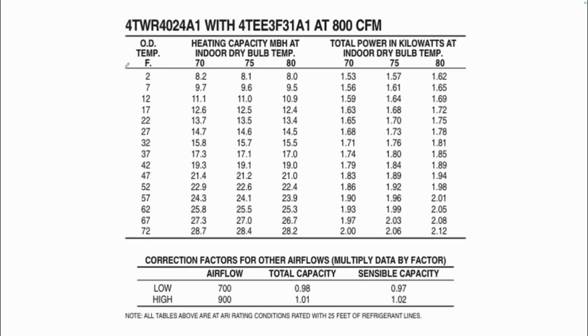But again, hopefully you see the benefit of this. Now, this is a Trane performance table here. This is a TWR4, which is a 14 SEER 2-ton unit that you see right here. And it shows you what the matching air handler is and the CFM. Now, down here below, it shows correction factors for other combinations. So if you're using a different air handler, it gives you a multiplier. Now let's blow this up a little bit.